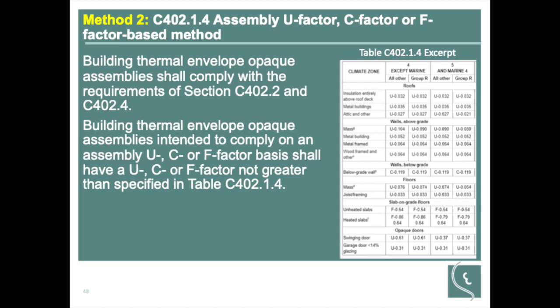This U factor table, when you get into the residential side, may be a much better way to comply when you end up with flat roofs on residential. Because residential does not have this classification of insulation entirely above roof deck, and so it requires R49 versus R30 continuous for the commercial side. So that's where these U tables might come in handy in that particular instance.